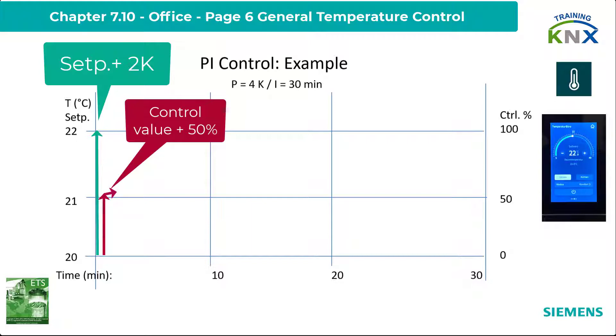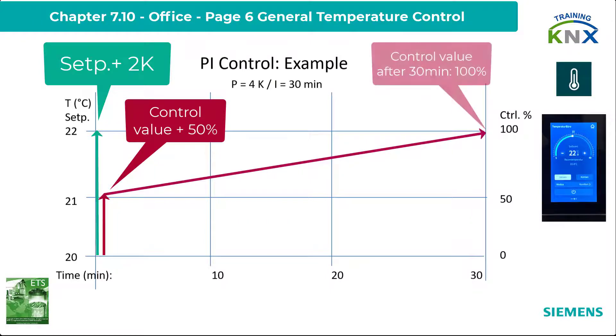A brief explanation of these two coefficients: a PI control works like this — if there is a change in the control difference (the difference between the setpoint and the actual value), the first thing that happens immediately is an adjustment of the control variable in proportion to the change via the P factor. Thus, if the control difference changes by 2 Kelvin with a P factor of 4 Kelvin, the valve is immediately opened further by 50% or closed, depending on the sign. The I coefficient amplifies the change in the actuator so the desired state — setpoint equals actual value — is reached more quickly. What the P coefficient does immediately, the I coefficient does again within the set time (here 30 minutes) in the same amount, but only if the control difference does not change.